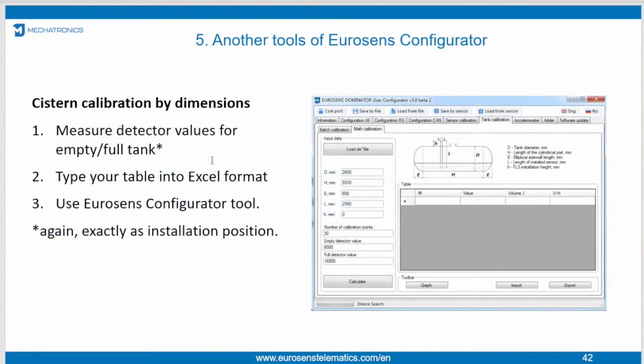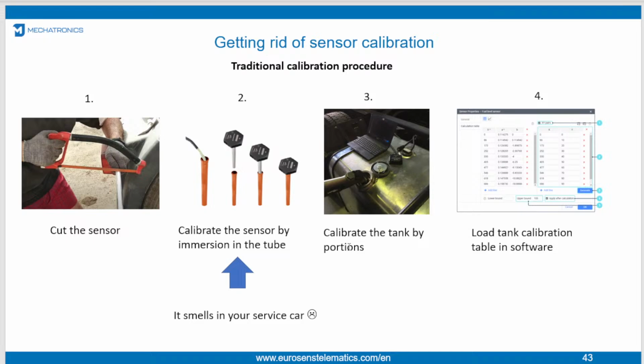And the last thing I wanted to tell you is how to get rid of sensor calibration. Remember, it was a procedure to teach the sensor its new length after cutting or extending. And many fuel level sensor vendors recommend this procedure.